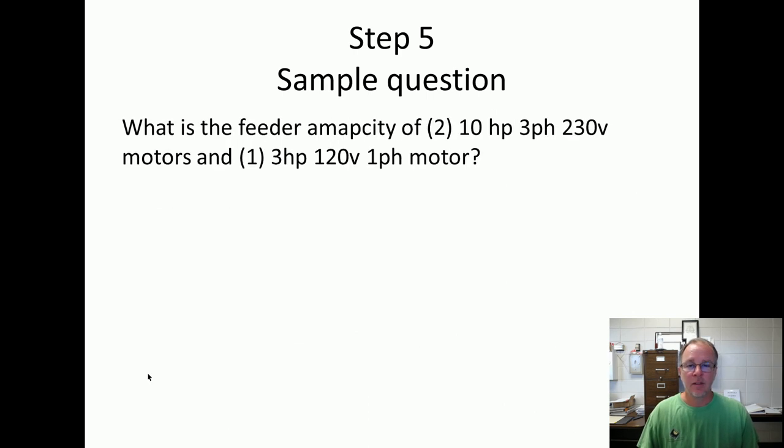Okay, here's the last one on step 5. What's the feeder ampacity of two 10 horsepower 3-phase 230 volt motors and one single phase motor? That's a tricky one because the 3-phase motors are handling all 3 lines. Well, the 3 horsepower single phase motor is just tapped off 1 line. So we're going to handle it off of 1 phase, and that's going to be your largest conductor.